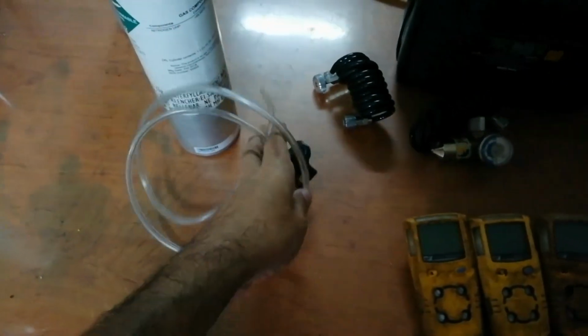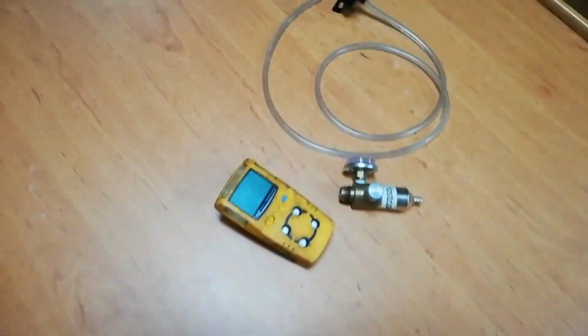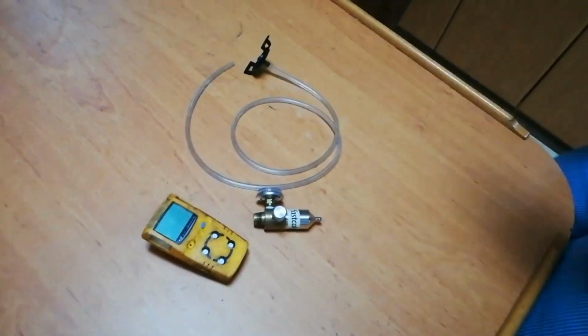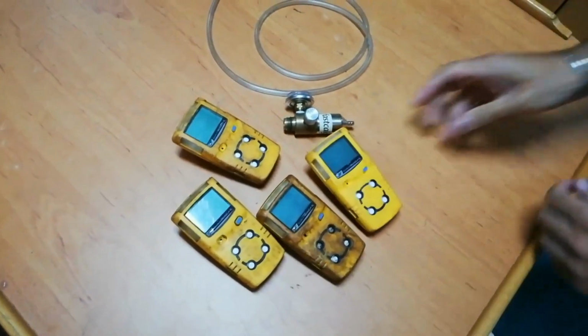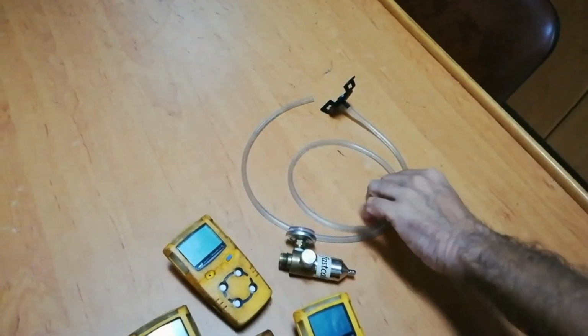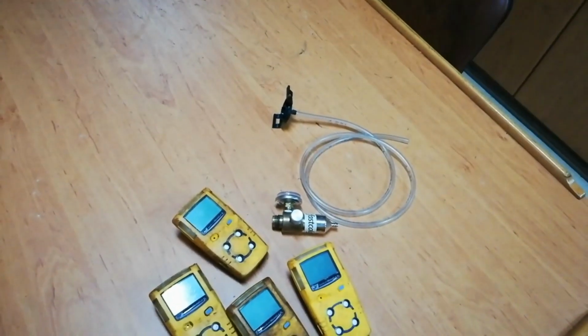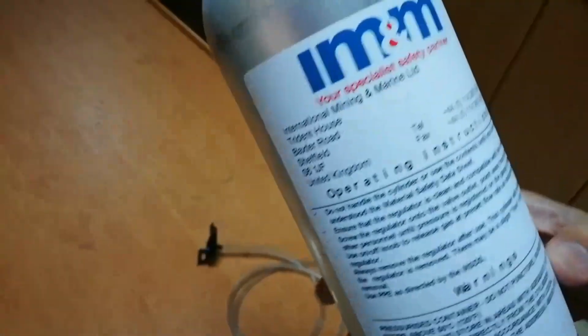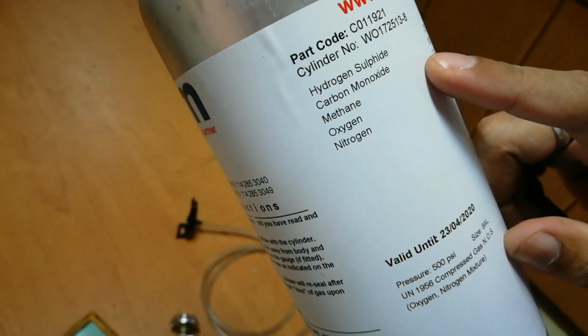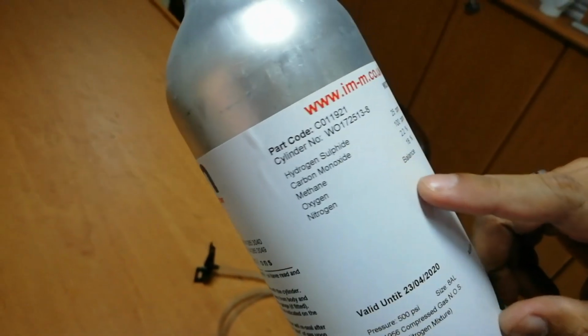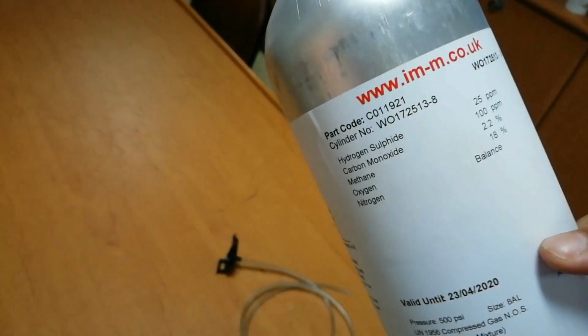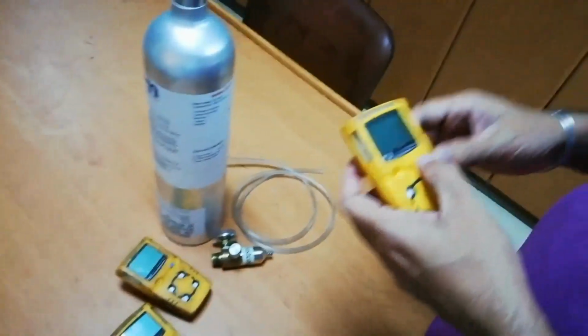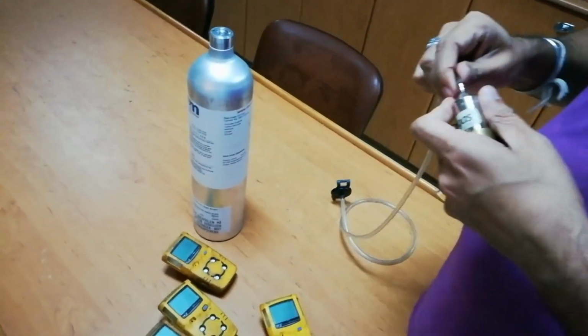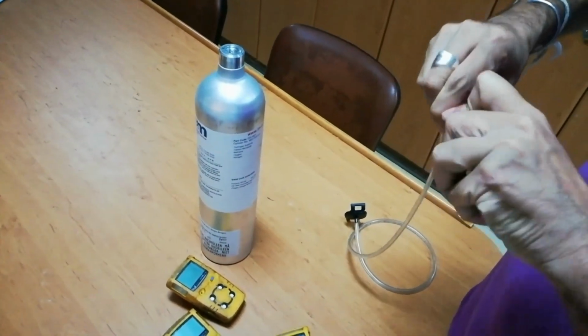I will make it three parts of video for the calibration. Okay guys, this is the first part of the video. First I am going to do the calibration for the Gas Alert Microclip XT multi-gas detector. I have four units, and I will use this fixed regulator of 0.5 liter per minute, the calibration hose and adapter, and this is my span gas for the calibration. Here you can see the content of this span gas: hydrogen sulfide 25 ppm, carbon monoxide 100 ppm, methane 2.2%, and oxygen 18%, balanced in nitrogen. We are using this span gas because this gas detector can detect and measure oxygen percentage, H2S, carbon monoxide, and LEL.